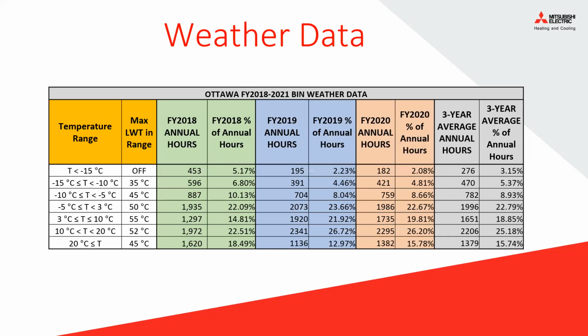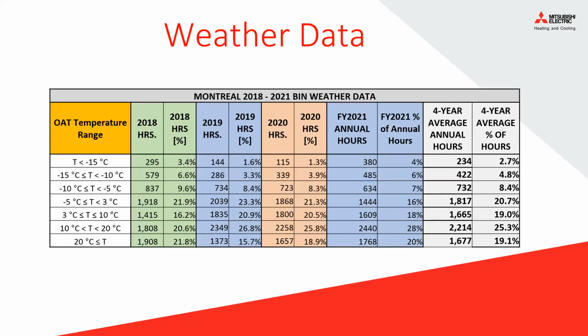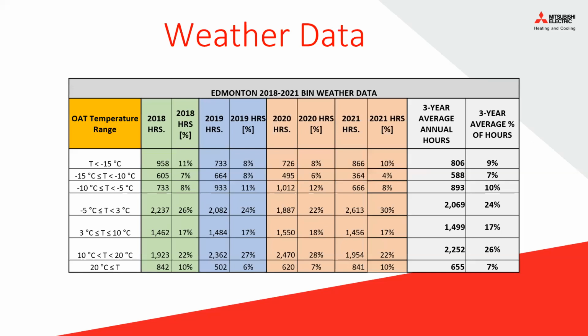This is the weather data for Ottawa, looking at a 3-year average. Evidence shows that we have 96% of the year spent above negative 15 C. And Montreal, 3-year average, 97% above negative 15 C. And Edmonton, it's up there, 90% of their time above negative 15 C, but they do see temperatures below negative 15. So that's when you're going to have a supplementary system that'll carry the load for that 10% of the time.